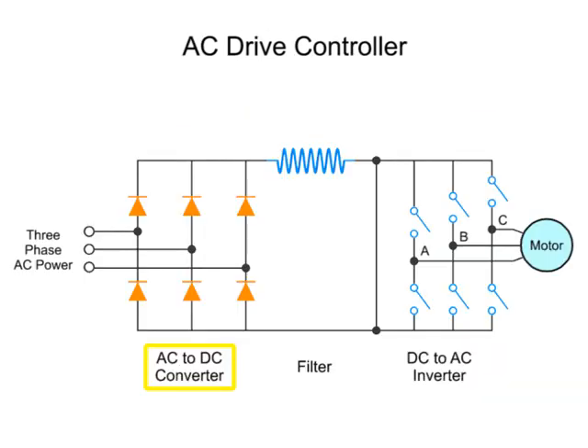The converter or rectifier component consists of an array of fast-acting switches that convert an incoming AC voltage to a pulsating DC voltage. The intermediate circuit acts as a filter and consists of a DC bus and associated circuitry. This stage of the wave conversion serves to stabilize and smooth the pulsating rectifier output to generate a constant DC voltage.